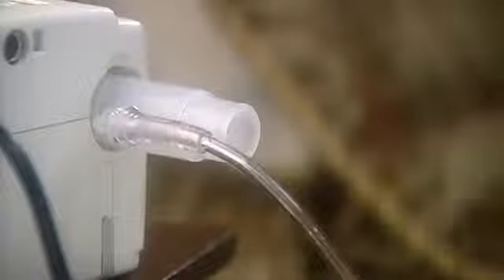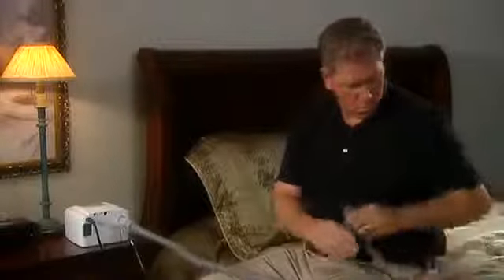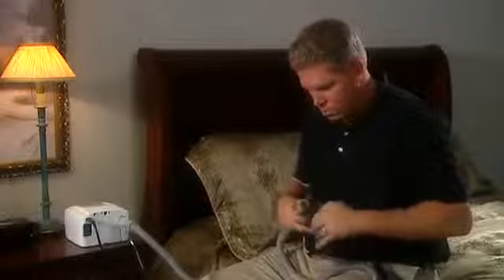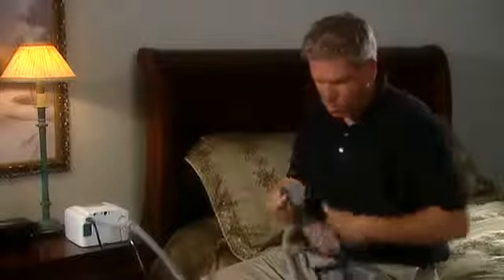If your physician has prescribed supplemental oxygen for treating your obstructive sleep apnea, you can order an optional oxygen adapter from your home health provider. Connect the oxygen adapter to the outlet port on the unit. Next, connect one end of the air supply tubing to the open end of the adapter and the other to the mask. If your mask is equipped with an oxygen port, your physician may request that you connect the source of supplemental oxygen directly to the mask. Other accessories can be connected to your device at the data port on the back of the unit. Only use accessories approved by DeVilbiss to prevent damage to your CPAP unit or accessory device.